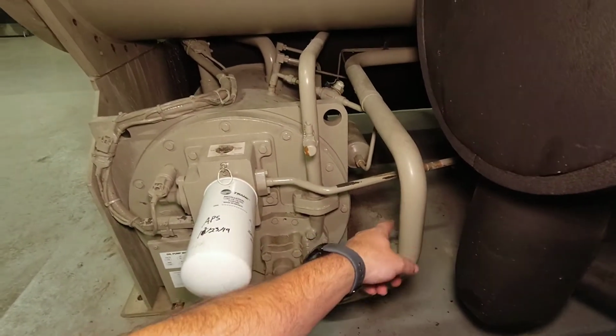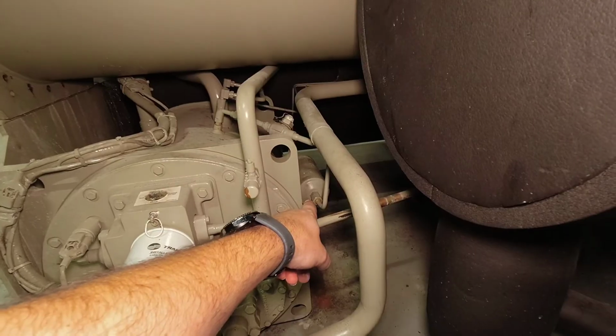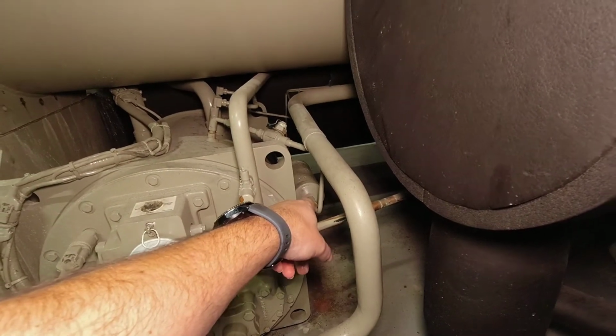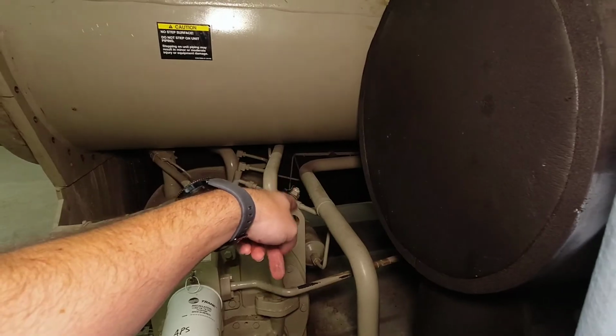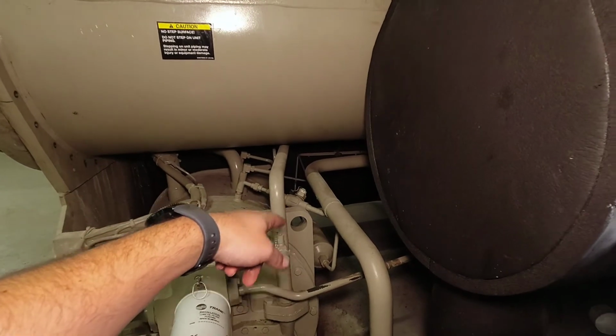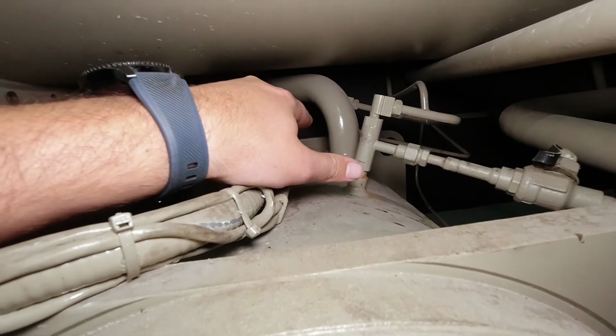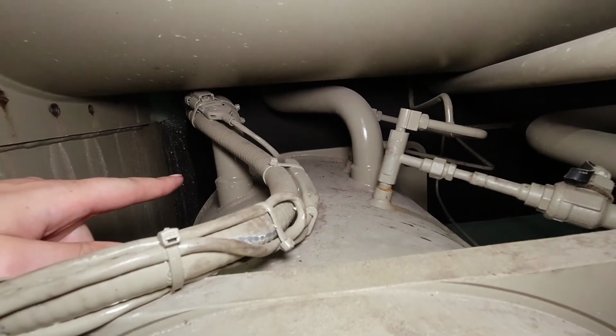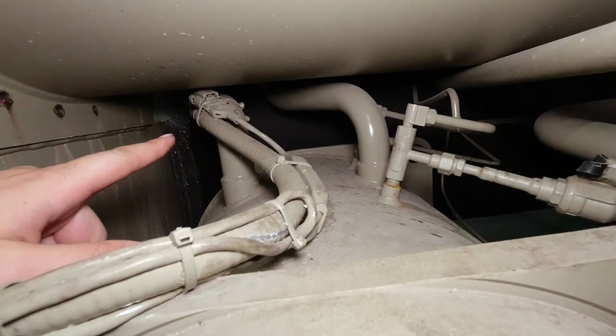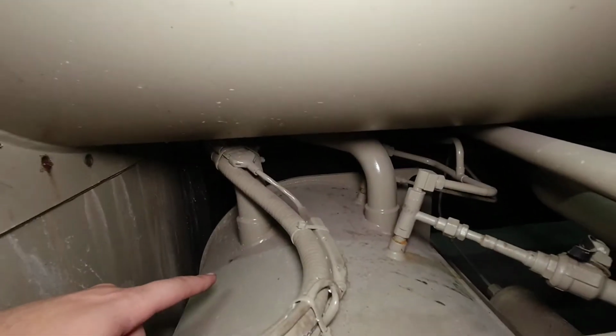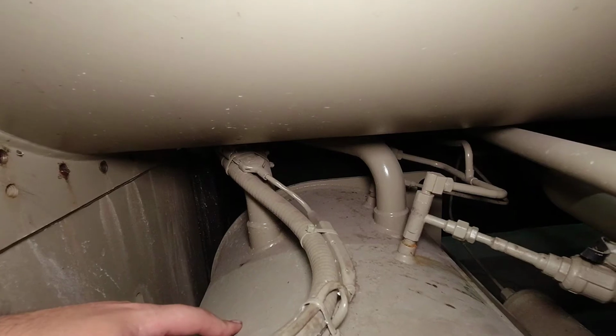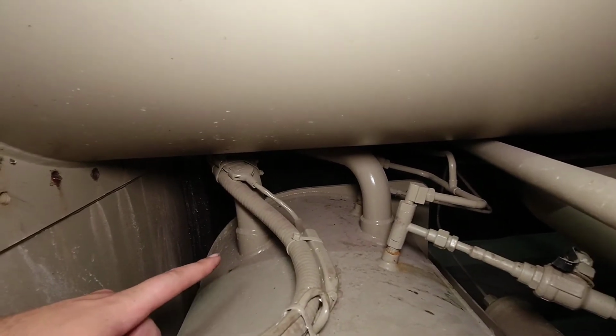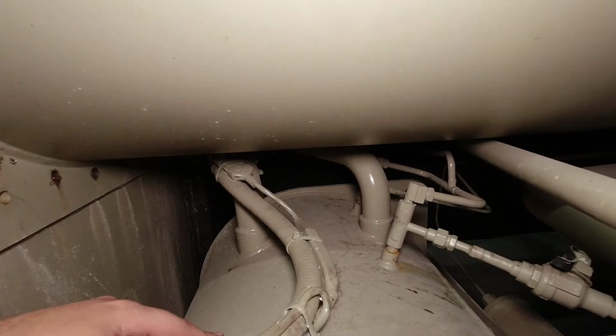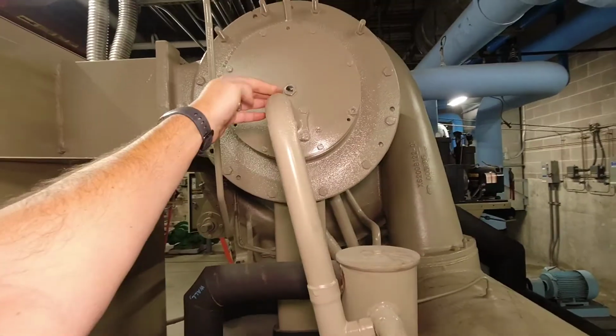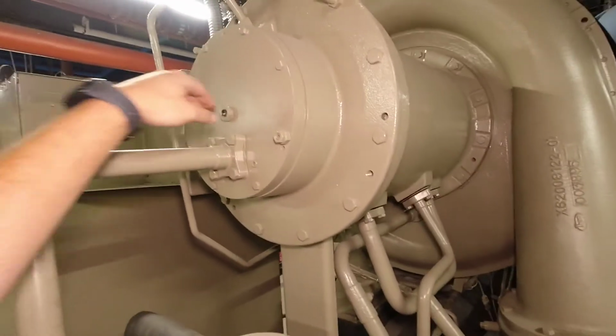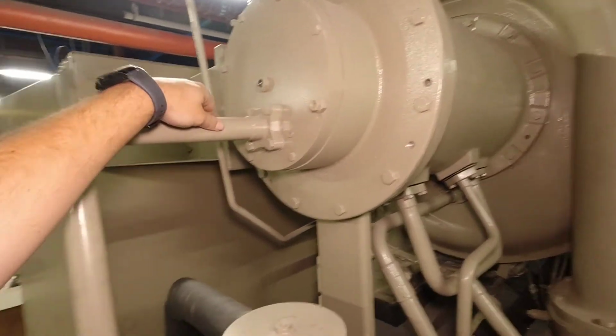This is a refrigerant pump. Get in there, that little canister style filter there is going to an oil return line coming off the bottom of the evaporator. So these lines on top are all part of your sump return lines, where it's dumping back into the oil sump, and you do want your oil sump to be at a lower pressure than your evaporator.